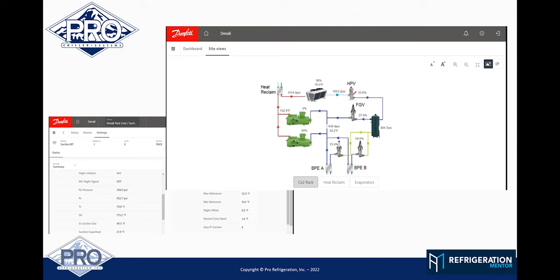My flash gas valve is probably going to open up. I expect that's going to open up a little bit to hold that down at my set point, which I know is 550. And then what are my expansion valves doing feeding into my brazed plates? So, it's all that right there just gives a really nice overview to say, yeah, it's looking like she's running pretty good right now.